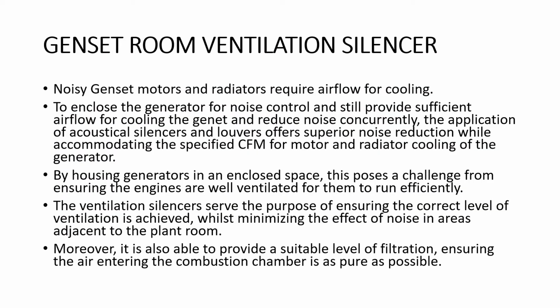So genset room ventilation silencer. Noisy genset motors and radiators require airflow for cooling. To enclose the generator for noise control and still provide sufficient airflow for cooling the genset and reduce noise concurrently, the application of acoustical silencers and louvers offers superior noise reduction while accommodating the specified CFM for motor and radiator cooling of the generator.